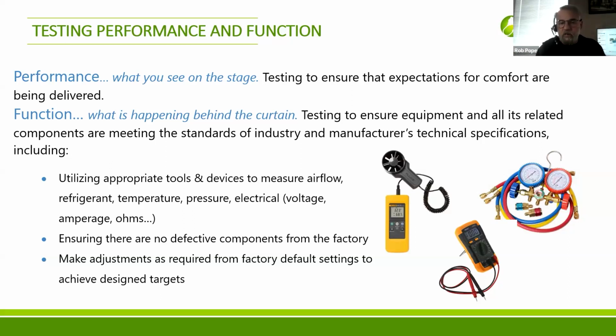You're measuring refrigerant charge, making sure there's no leaks, making sure there's enough refrigerant as per your manufacturer's requirements. Temperature, you're measuring temperature of a number of things. Temperature rise between the return and supply air, for example, and temperature in the rooms, the ambient temperature, outdoor temperature, part of all of this is calibrating the sensors. You're checking pressures, the total external static pressure of the system.